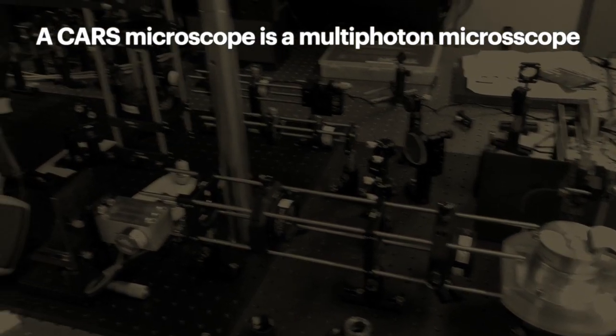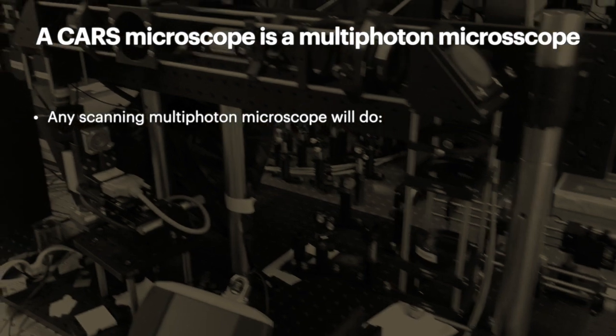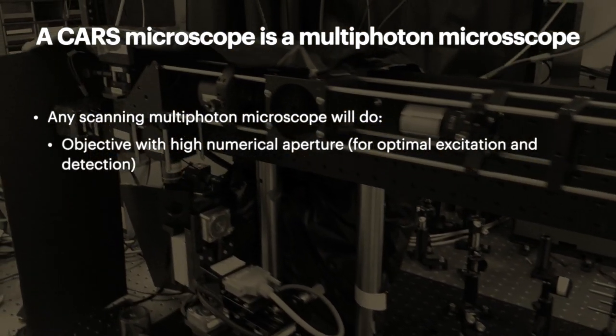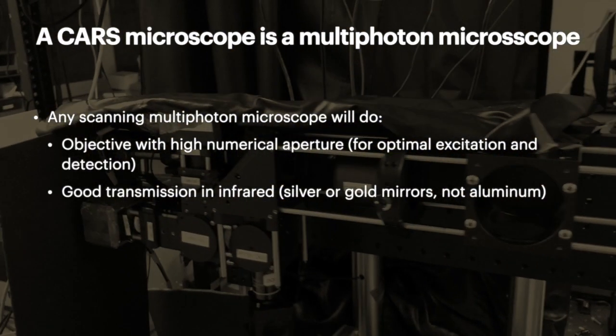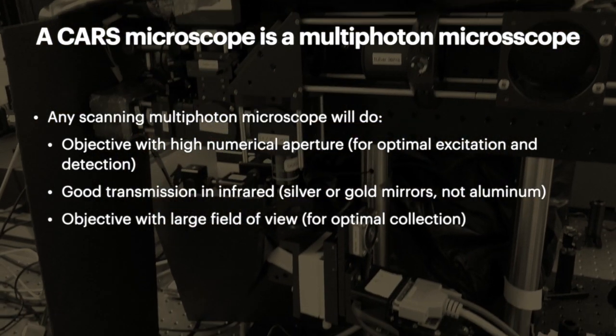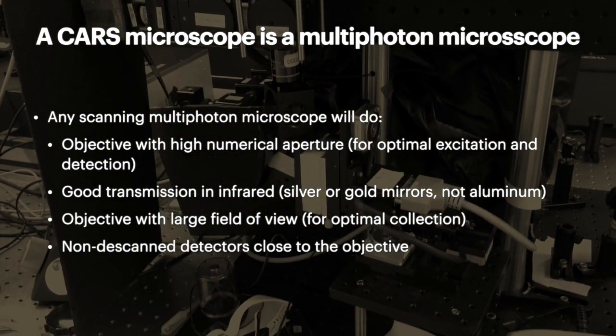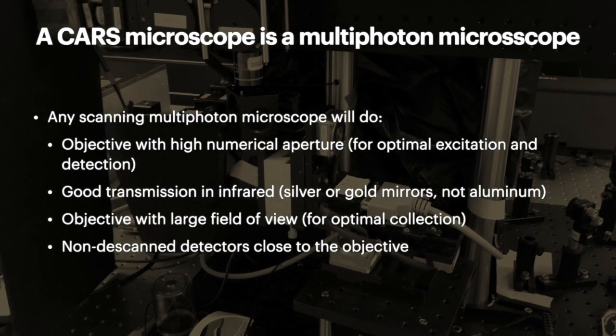A CARS microscope is a multiphoton microscope. Therefore, any scanning multiphoton microscope will do. So you'll need an objective with high numerical aperture, good transmission in the infrared, an objective with a large field of view, and non-descan detectors close to the objective. We use a video rate microscope based on a polygonal mirror scanner.